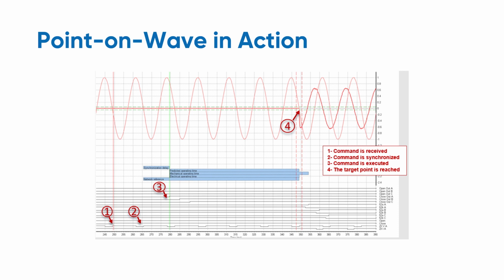So it's literally a middleman. It takes the signal and then passes it to the circuit breaker at the right point. And as you can see there, point 4, that indicates the target angle that we're trying to hit. And you can see there, that's when the current and the voltage has appeared and the circuit breaker is closed and energized the transformer at that point.